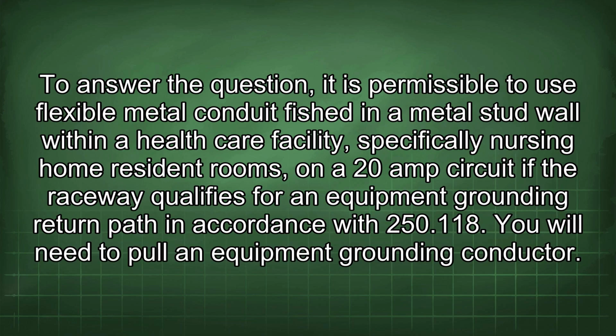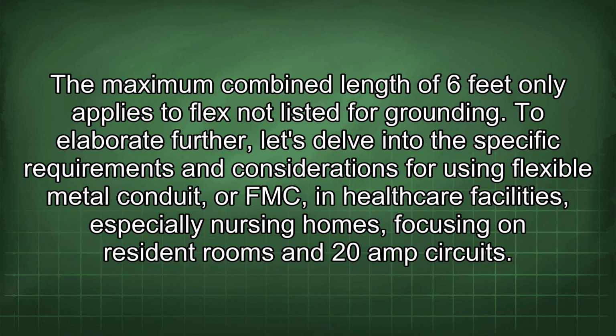To answer the question, it is permissible to use flexible metal conduit fished in a metal stud wall within a healthcare facility, specifically nursing home resident rooms, on a 20 amp circuit if the raceway qualifies for an equipment grounding return path in accordance with 250.118. You will need to pull an equipment grounding conductor. The maximum combined length of 6 feet only applies to flex not listed for grounding.